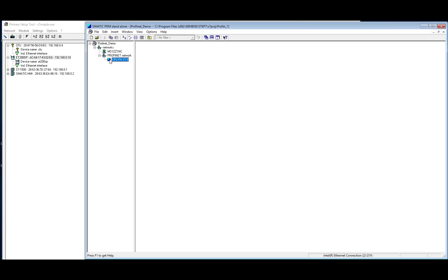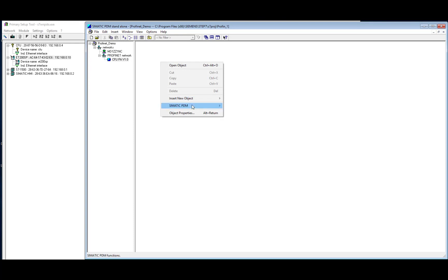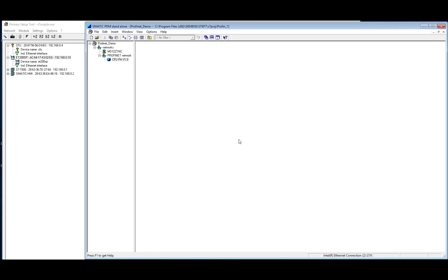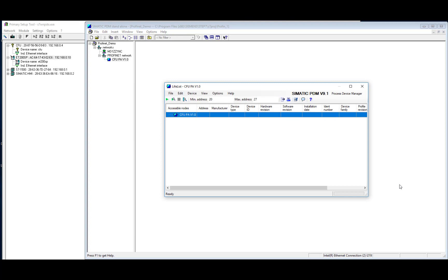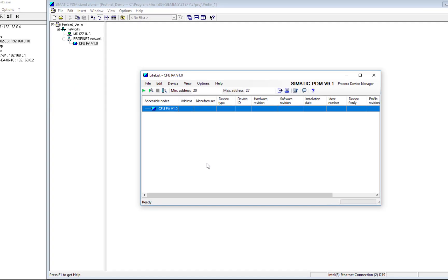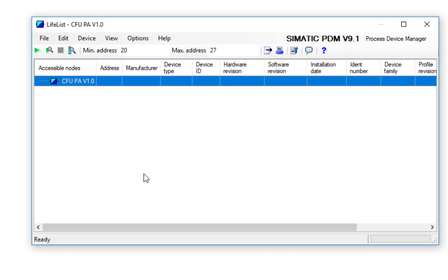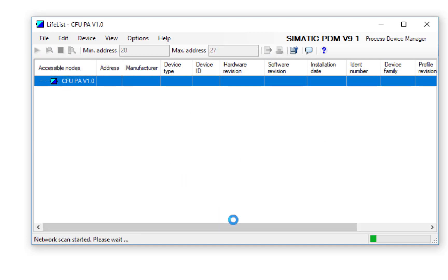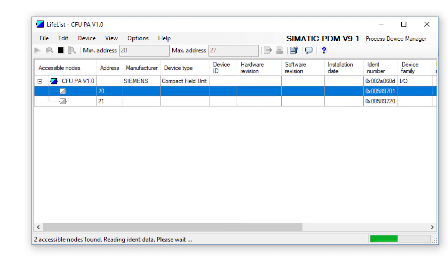What we need to do now is see physically what is connected to that Compact Field Unit. So over here on the right-hand side, go to PDM, and we can start lifelist. So on the Compact Field Unit, we can have up to eight Profibus PA devices. The Compact Field Unit automatically addresses them in this range, 20 to 27, but we just need to see what they are. So if we click on the Scan button, it's found address 20 and 21.